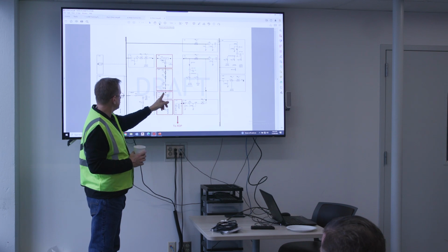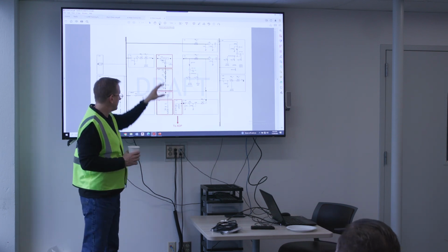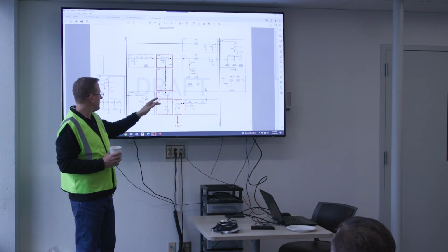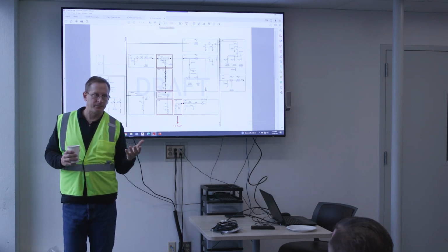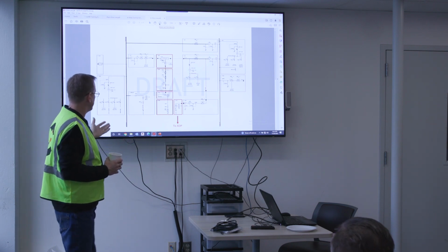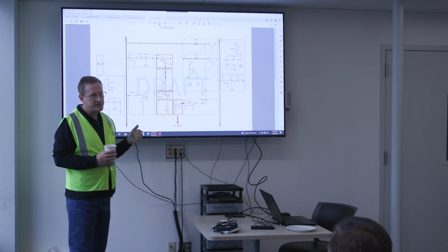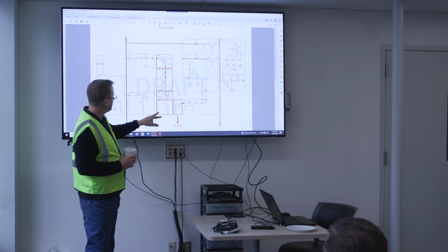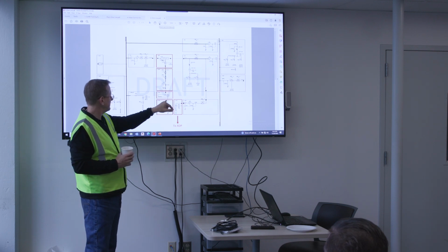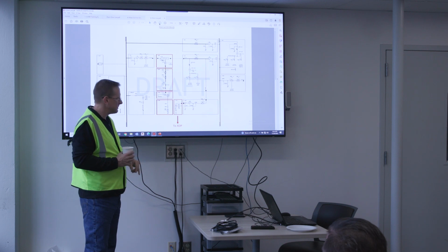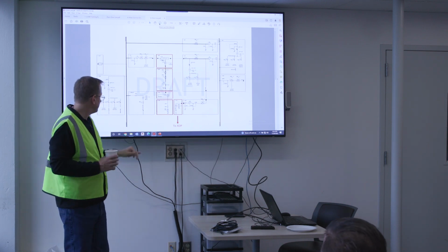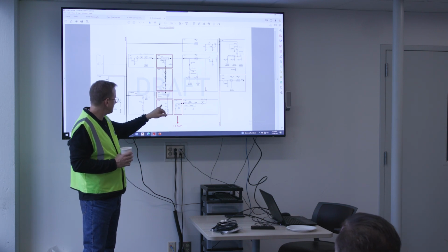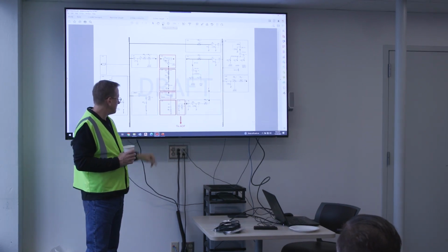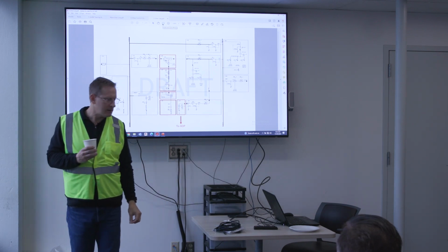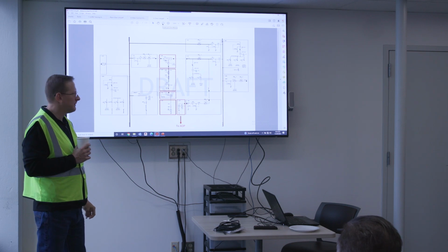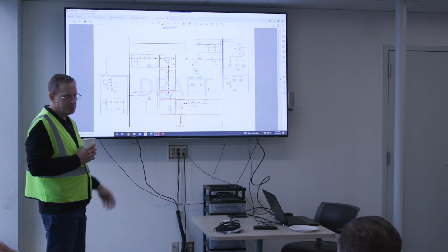Then, of course, you come from that into our junction box of our generator. This is all medium voltage, of course, and so that's the feed into our generator junction box for the alternator. Obviously directional for either operating as a motor or a generator. And then we also have an LRG system, which basically the neutral of the alternator is connected through a resistance ground, and that was provided by Stanley, I think, or McKinstry provided this. That's just basically providing you an LRG system in case you would have a ground fault of some sort, to enable the system to protect against those.